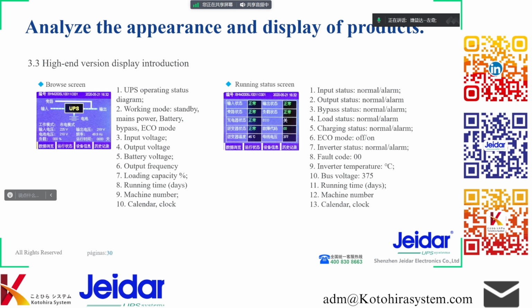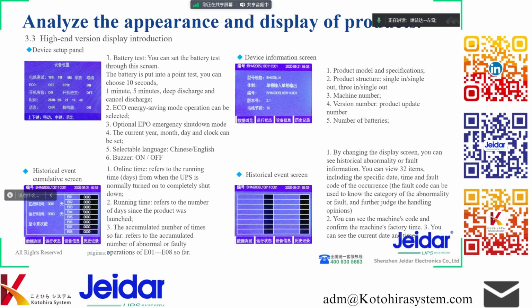The high-end version display includes a browse screen, running state screen, device setup panel, device information screen, historical event cumulative screen and historical event screen. About the historical event screen, I believe everyone in the industry knows that a small UPS has a problem. It will show a fault code. You only know that it has a problem now, but you don't know the cause and effect and the specific fault point. So we designed a history page diagram. None of the current mainstream UPS have the function of recording the process from startup to failure. Based on this pain point, we added a new function.